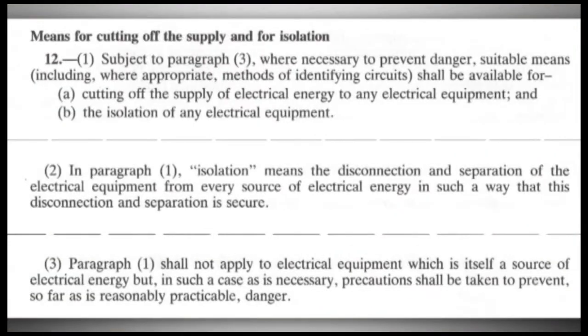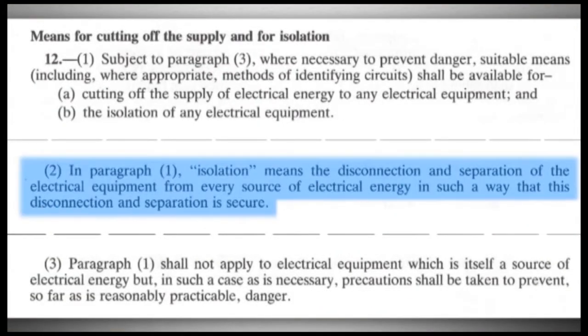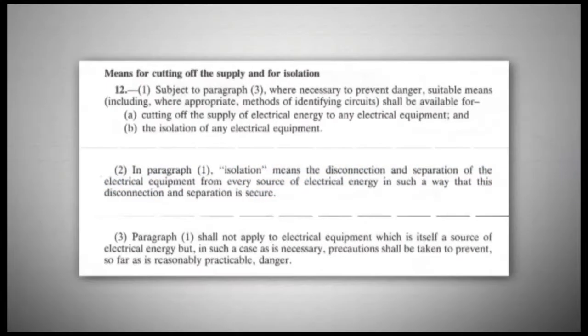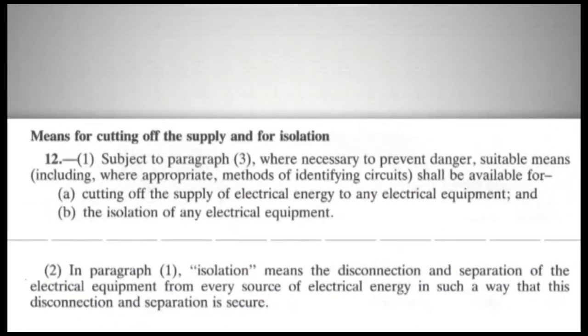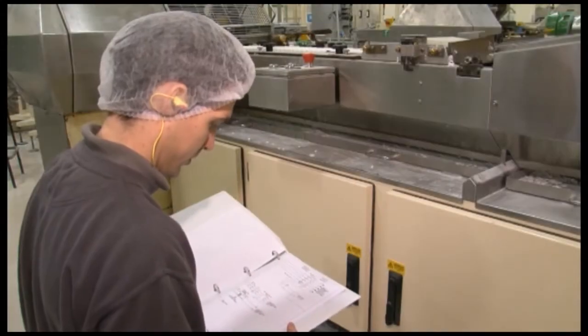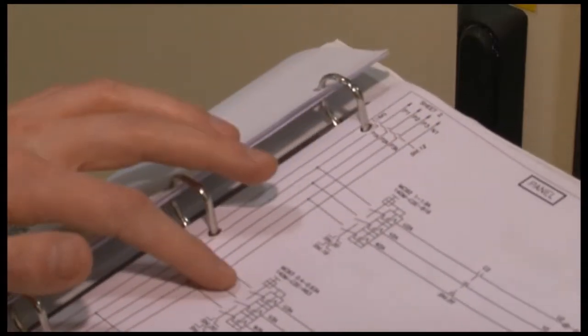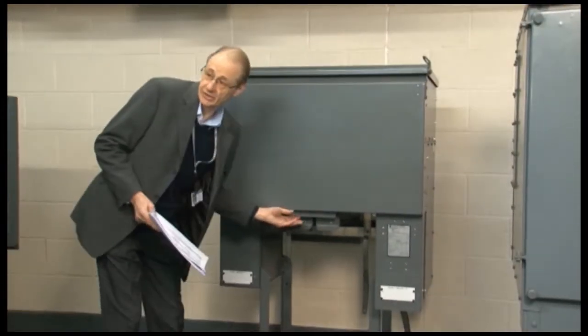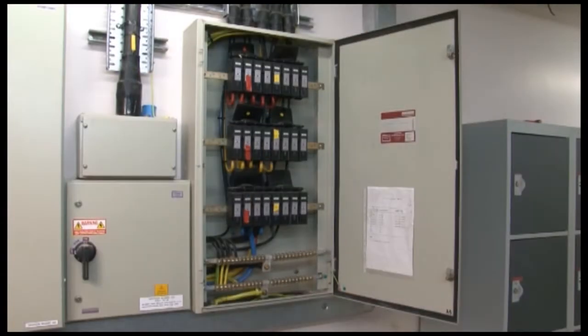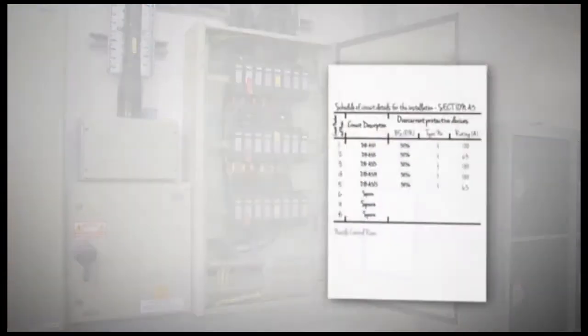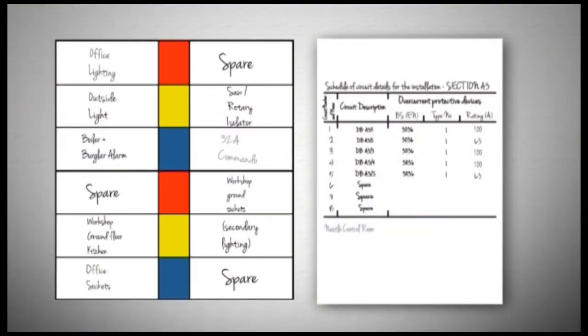To begin with, Regulation 12 not only contains the legal definition of isolation, which we gave you earlier, it also recognises that it's important to identify the right circuit or piece of equipment which you're going to isolate, mentioning methods of identifying circuits. In practice, these are up-to-date drawings of the system from the transformer to the final circuits, and a well-labelled installation with circuit schedules in all the distribution boards.